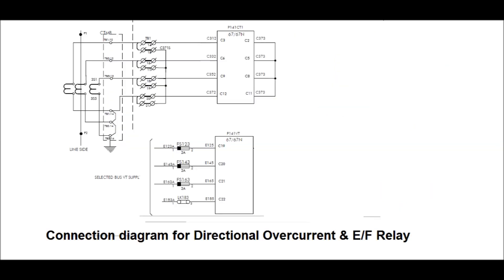Now, the connection diagram for MICOM P141 directional overcurrent relay has been shown in this diagram. It takes the PT voltage at the port as shown and CT current as shown in the upper portion of the diagram. The CT polarity must be correct, otherwise for a fault on the transmission line section, it may not sense the fault as the directional feature is given in the relay. That is, the S2 terminal should be shorted for giving the directional forward feature in the transmission line, and the CT must be connected in proper polarity as shown in this diagram.